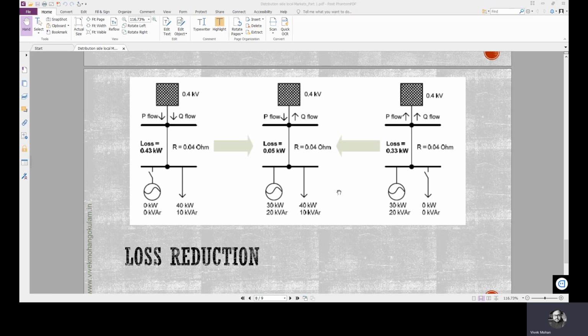Now initially the load is disconnected here. When the load is connected, what happens is the P flow towards the upstream grid is going to be reduced because 40 is here, right? So in this case 30 kilowatts is going to the grid. In the other case only 10 is coming from the grid, right? 10 is coming from the grid. In this case 30 is going towards the grid. So that also reduces the loss because of connection of this load. The loss is reduced to 0.05 kilowatts.